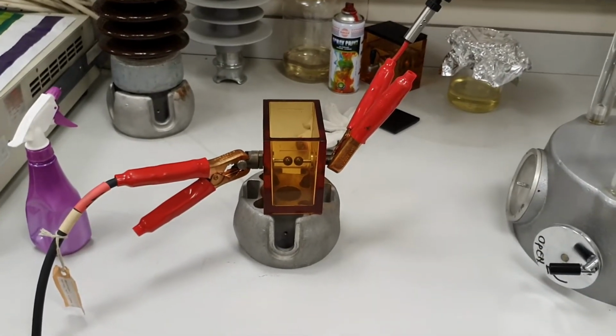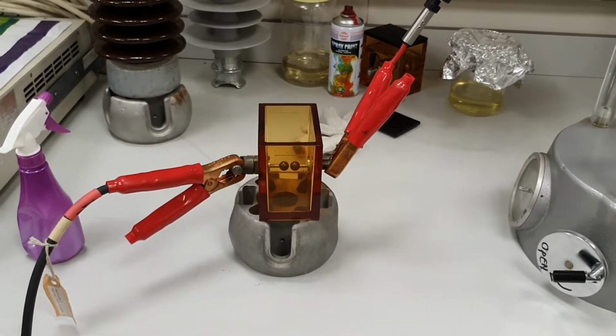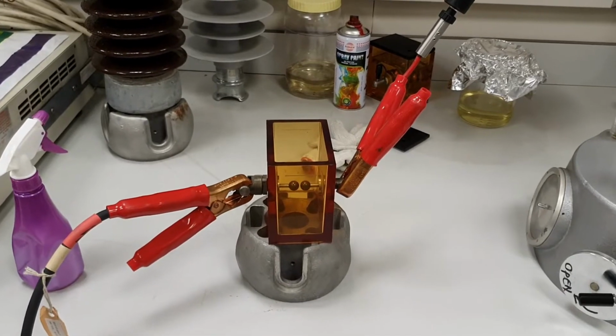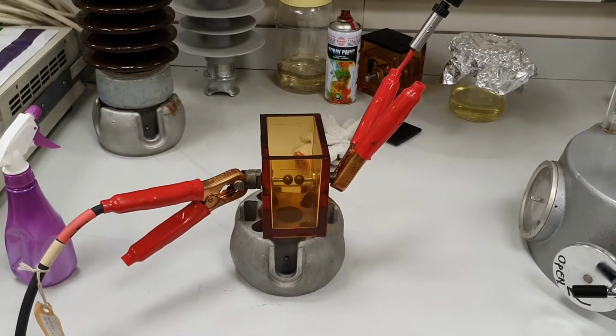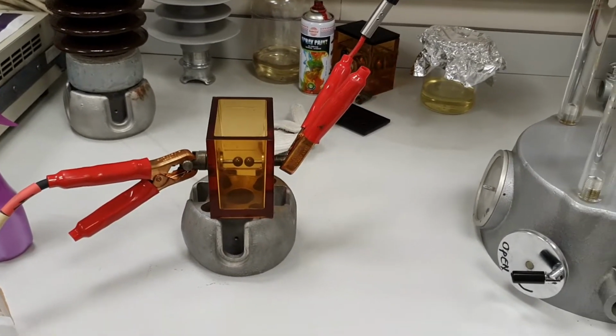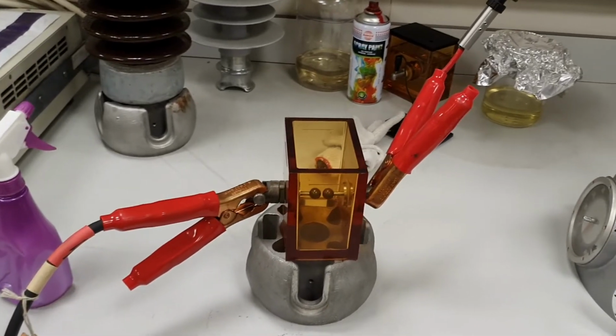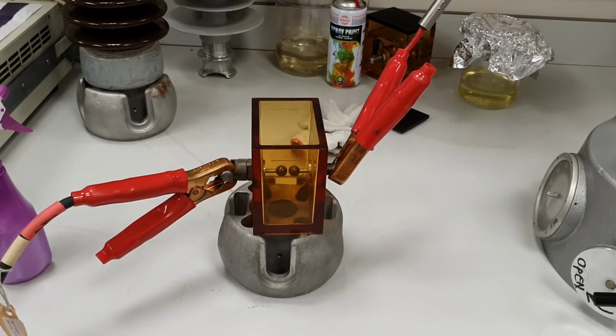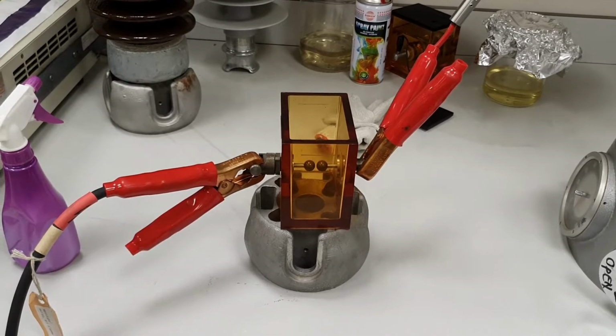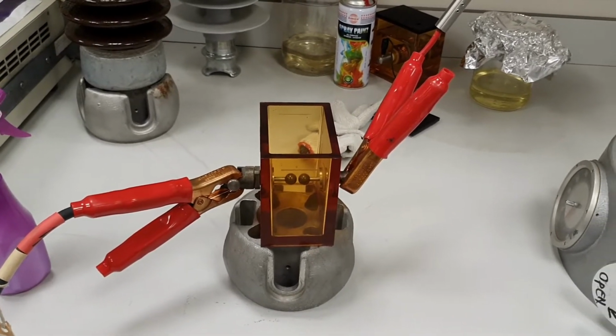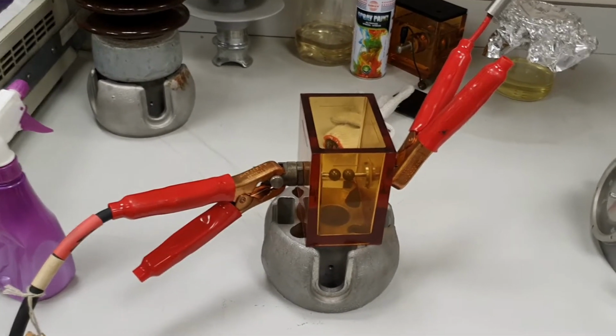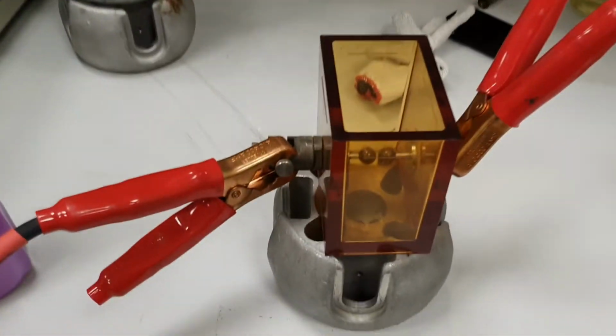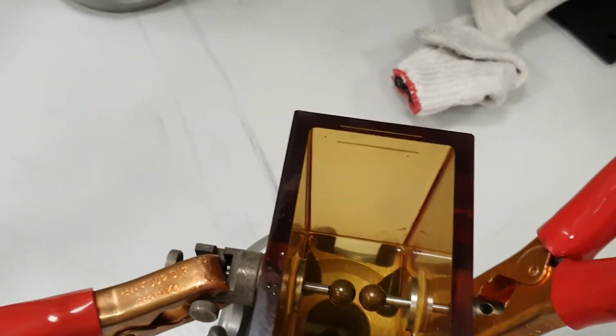So you will have this test cell empty. Now we'll be finding tan delta for the air. So this will be C0 for your measurements for finding the permittivity. You will repeat the same procedure as mentioned earlier for the first two cases and find whatever value of tan delta there. Then we will have this test cell filled with the oil.